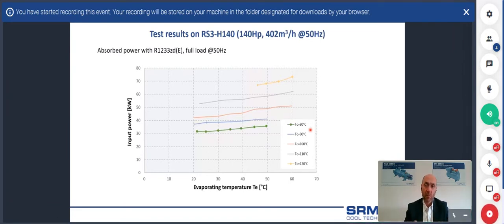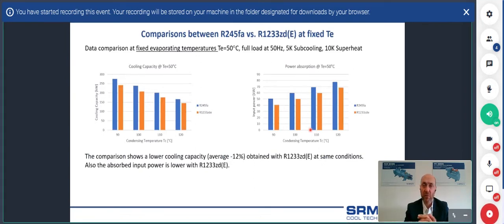So this graph shows most of the results on the compressor, and we use these results to make the comparison between the 245FA and the 1233ZD data. These first two graphs are made by maintaining fixed the evaporating temperature at 50 degrees C and varying the condensing temperature between 90 and 120 degrees C. We have the graph on the left showing the cooling capacity, and the graph on the right showing the input power. The first look indicates that the cooling capacity of the 1233 is lower than that expressed with the same compressor with the 245FA. This difference is around 12% lower. In the same way, the input power is also lower for 1233ZD.